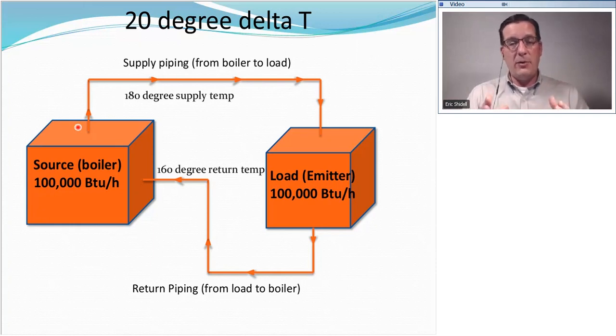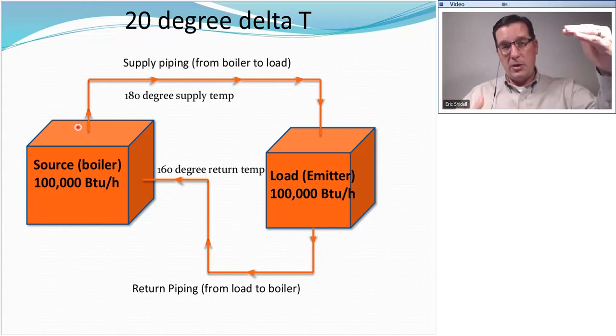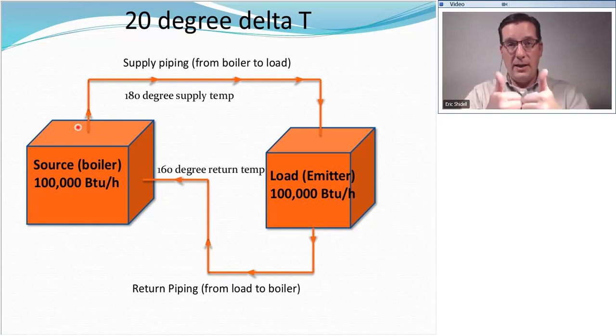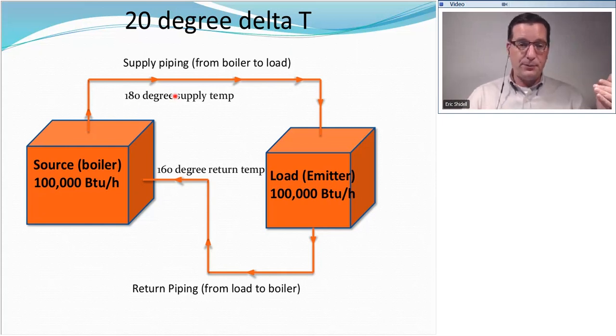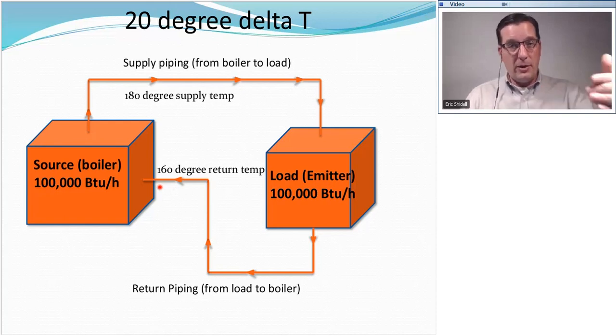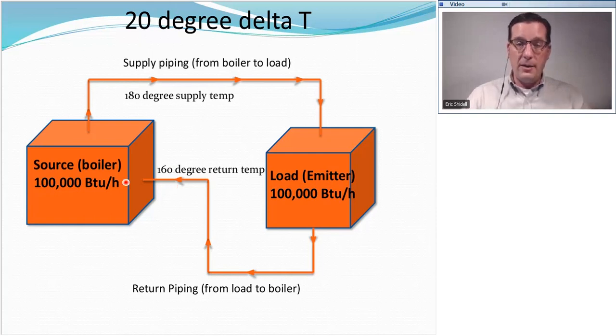Now, as I said earlier, the greater the temperature difference, the faster the heat transfer, right? So it makes sense that the greater the temperature difference across the boiler, the better the heat transfer, and that's true. But check this out. If our standard hot water supply temperature is 180 degrees, which it is for all of the supply systems, the piping systems, and the emitters we talked about so far, then the standard return temperature would then be 160 for a 20 degree delta T. But what if we had a 40 degree delta T? That would be better for heat transfer, but then we're getting into that cold water coming back to the boiler. We're worrying about condensing temperatures and a condensing heat exchanger. That's one reason why our 20 degree delta T is what it is.